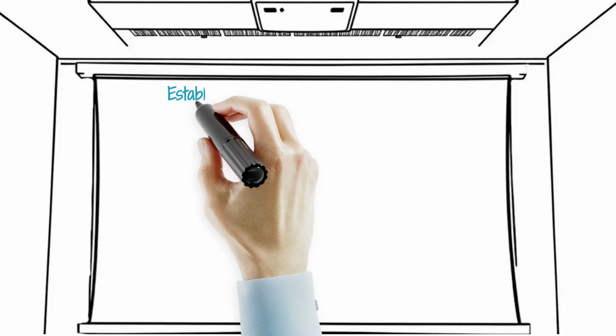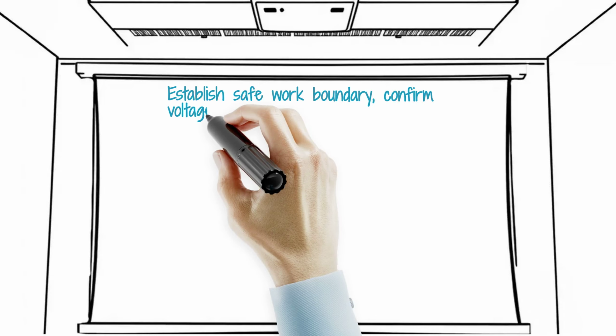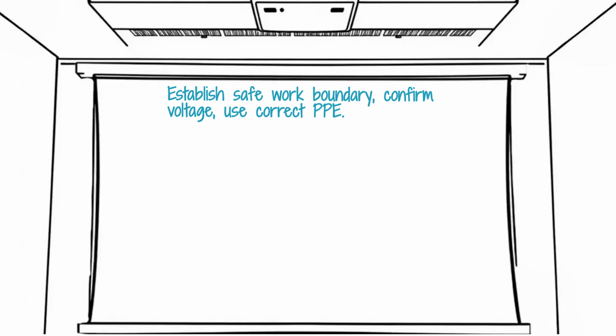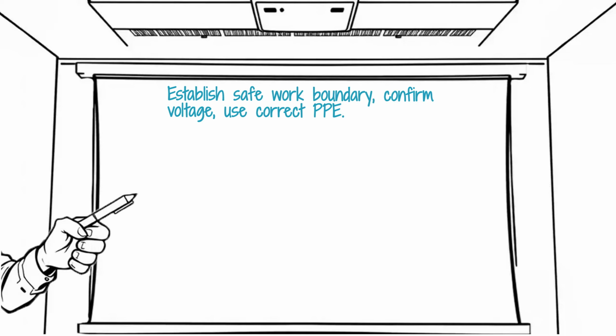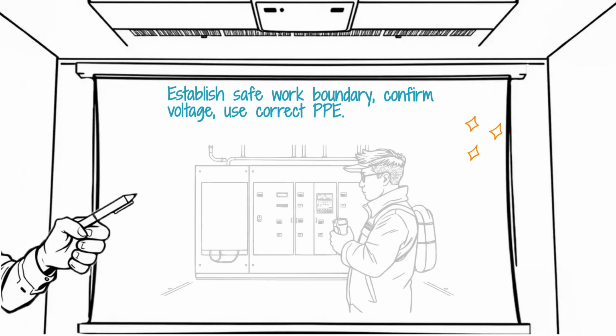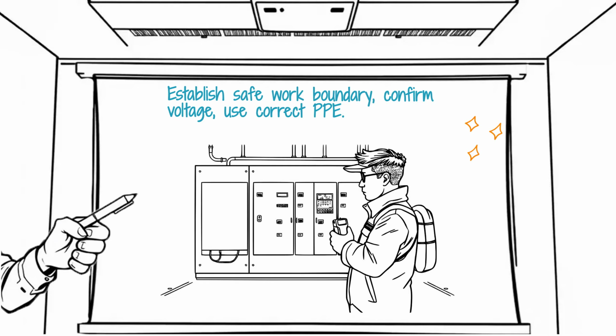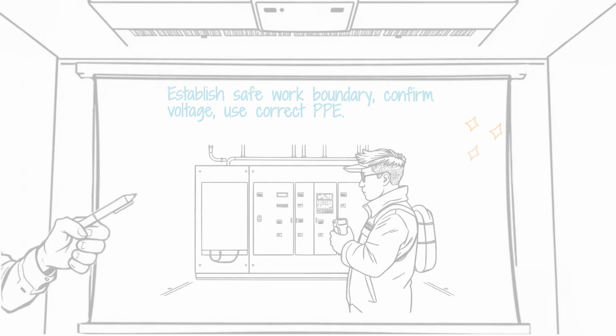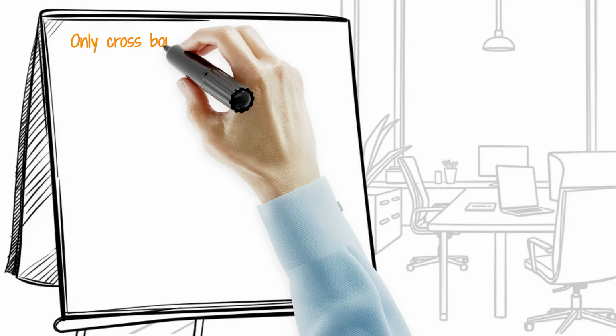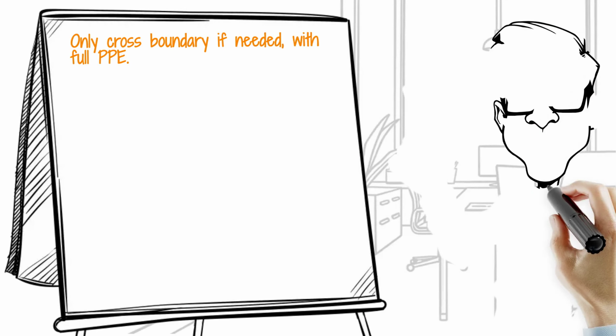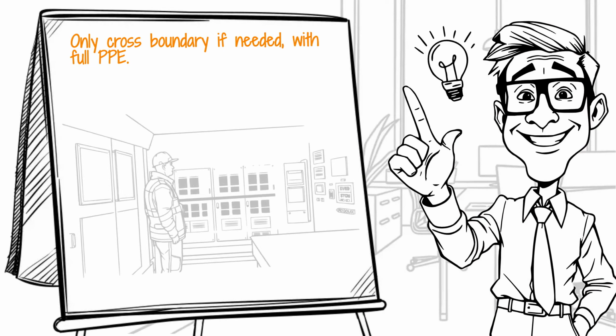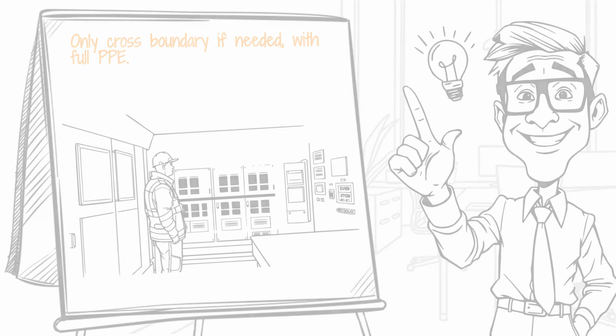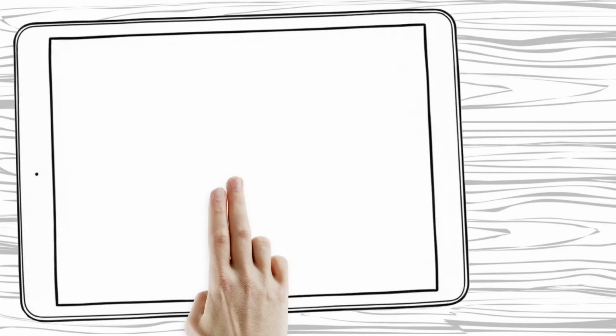The fourth step is establishing a safe work boundary. Before opening the panel, verify the voltage using a rated, tested non-contact voltage detector. Once confirmed, the worker must stay outside the established restricted approach boundary and only enter the limited approach boundary when wearing the appropriate PPE. Never cross the restricted boundary unless absolutely necessary and with the full arc flash PPE barrier in place. The fifth step is procedure and tool control.